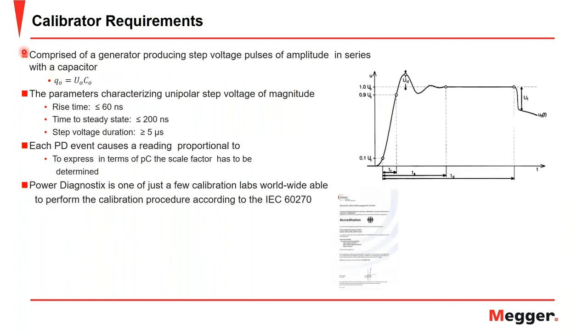The IEC 60270 does have calibrator requirements. As we stated, the calibrator is comprised of a generator producing a step voltage pulse of amplitude in series with a capacitor. And going over some of these parameters of the IEC 60270 characterizing the unipolar step voltage, your rise time must be less than or equal to 60 nanoseconds, which is that point TR here, from this point to this point here.